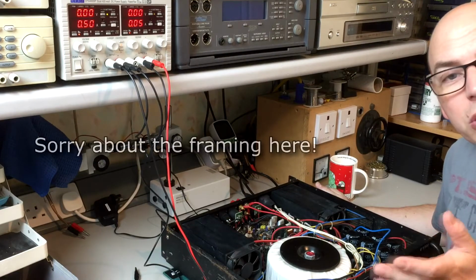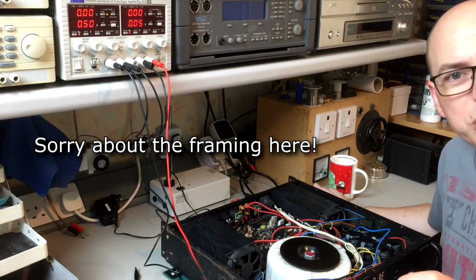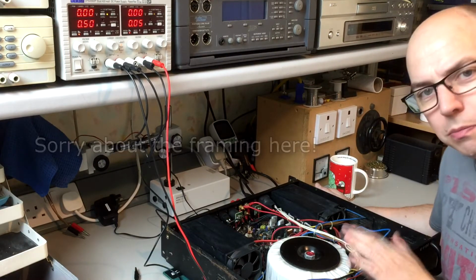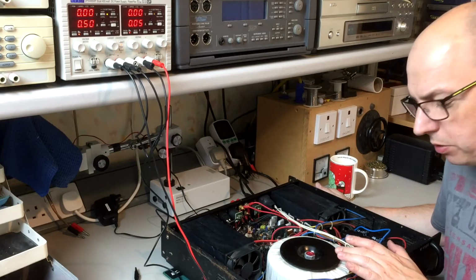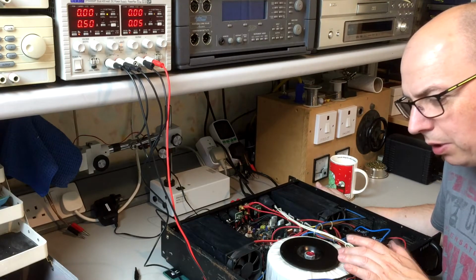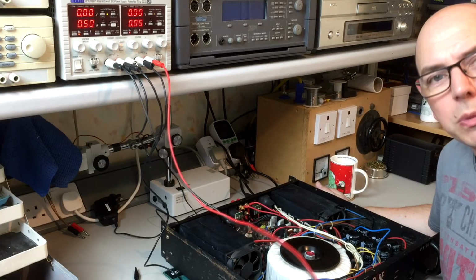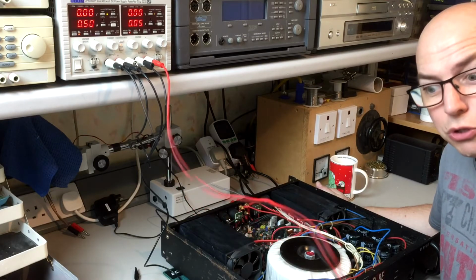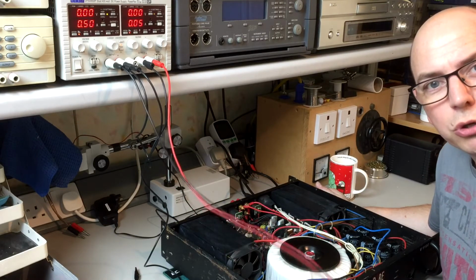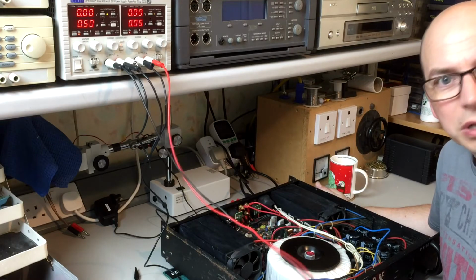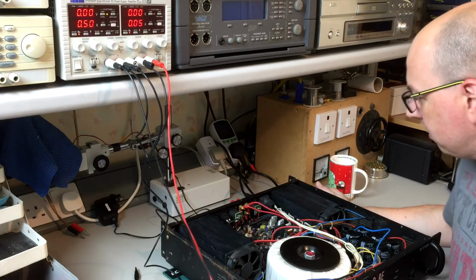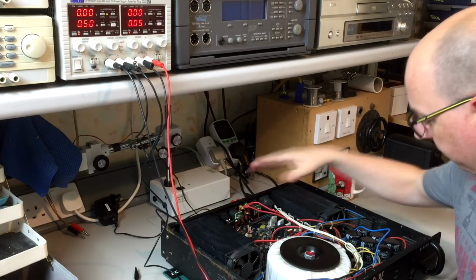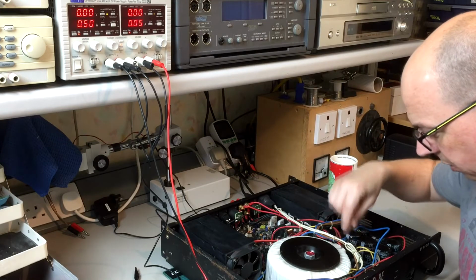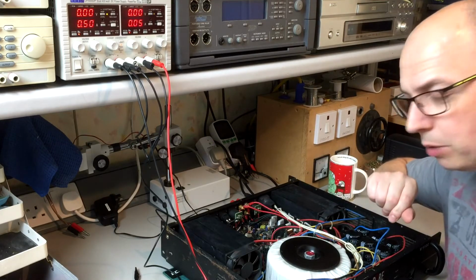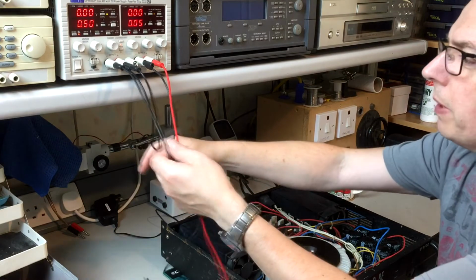If you've followed any of my other repairs, you'll know this is fairly standard procedure for me. I'll try and get the low voltage power supplies up, see if we can start applying high voltage safely via a power supply to ensure that if there are any faults, we're not going to cause high current and damage anything else. So I've applied the mains connection for the low voltage winding, so when we turn on we're going to get that low voltage output. I just need to connect my power supply now.